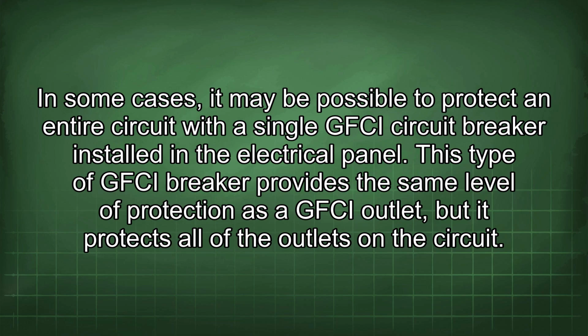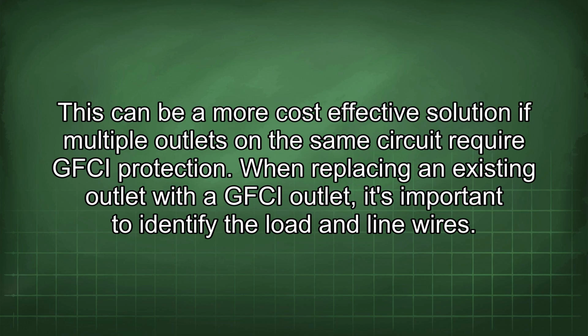In some cases, it may be possible to protect an entire circuit with a single GFCI circuit breaker installed in the electrical panel. This type of GFCI breaker provides the same level of protection as a GFCI outlet, but it protects all of the outlets in the circuit. This can be a more cost-effective solution if multiple outlets on the same circuit require GFCI protection.